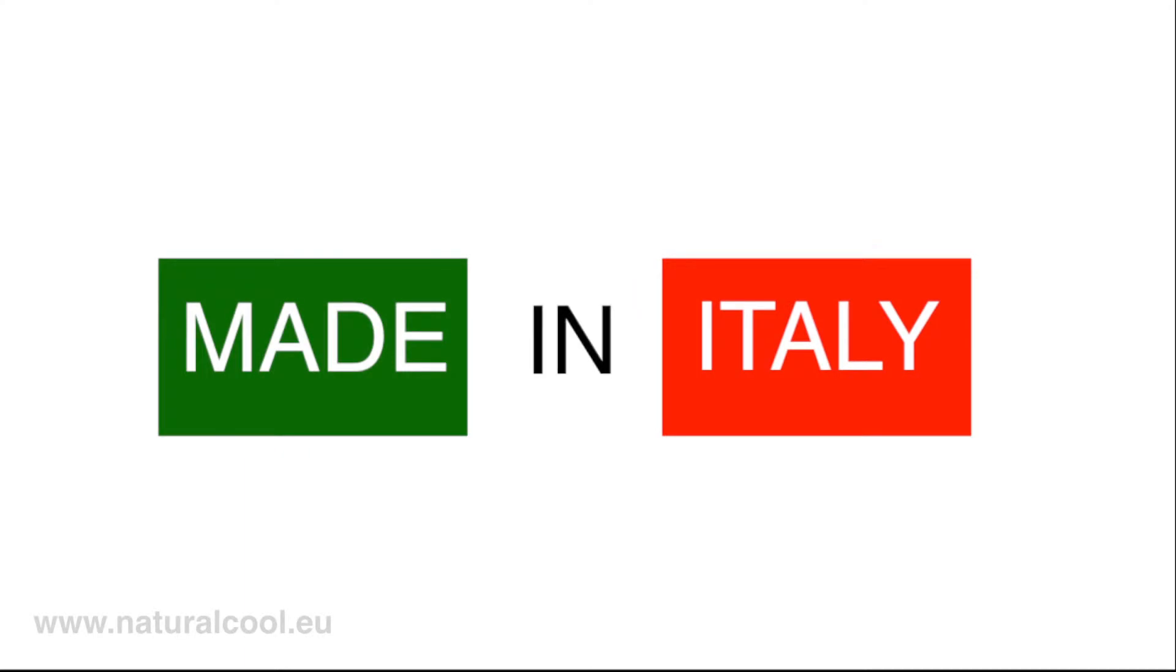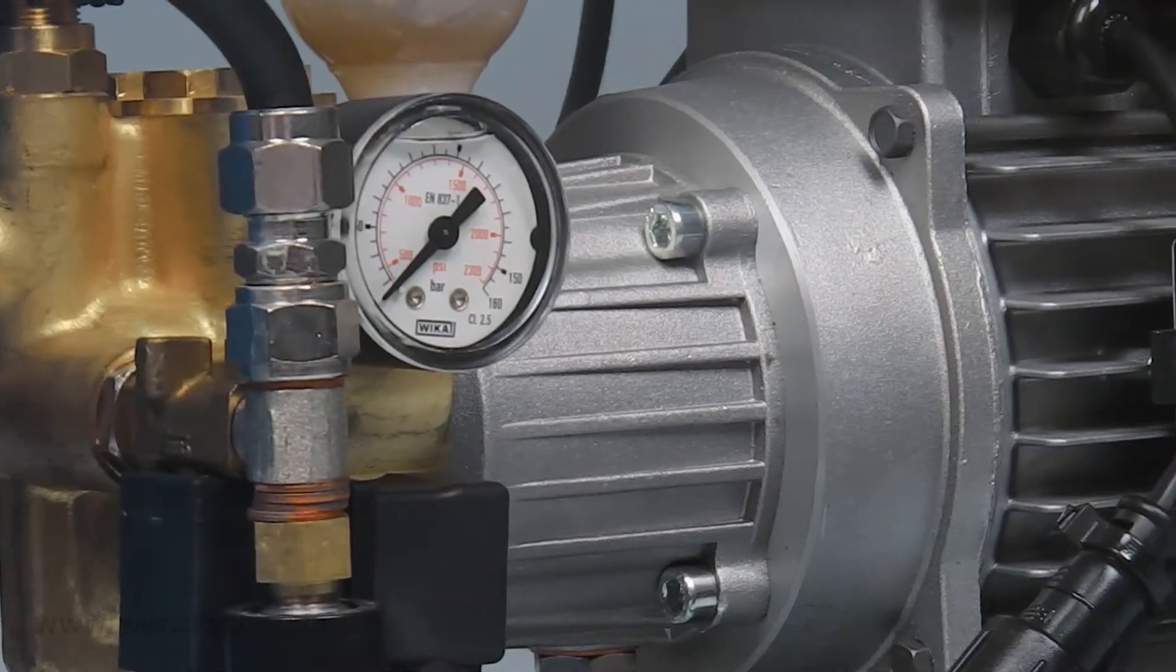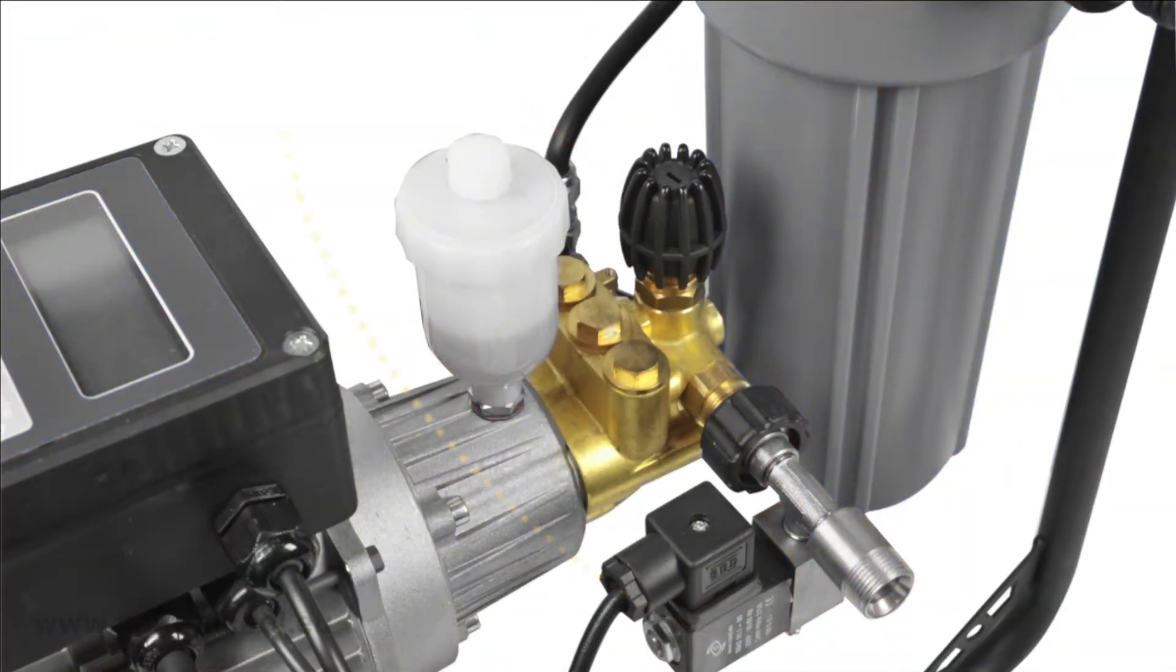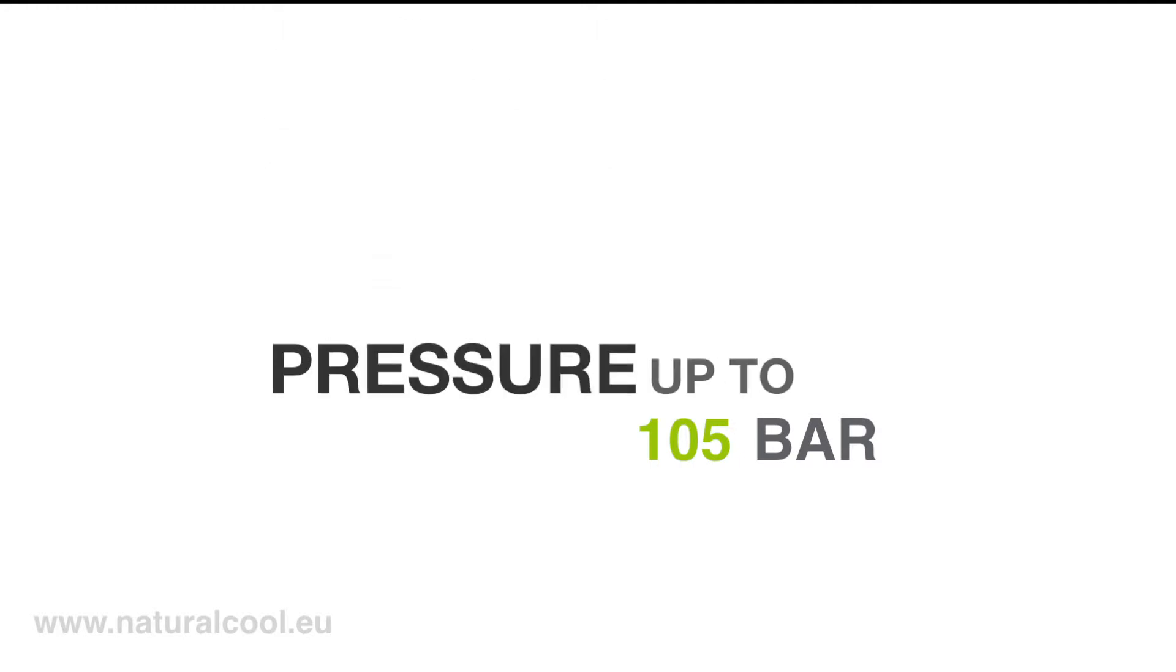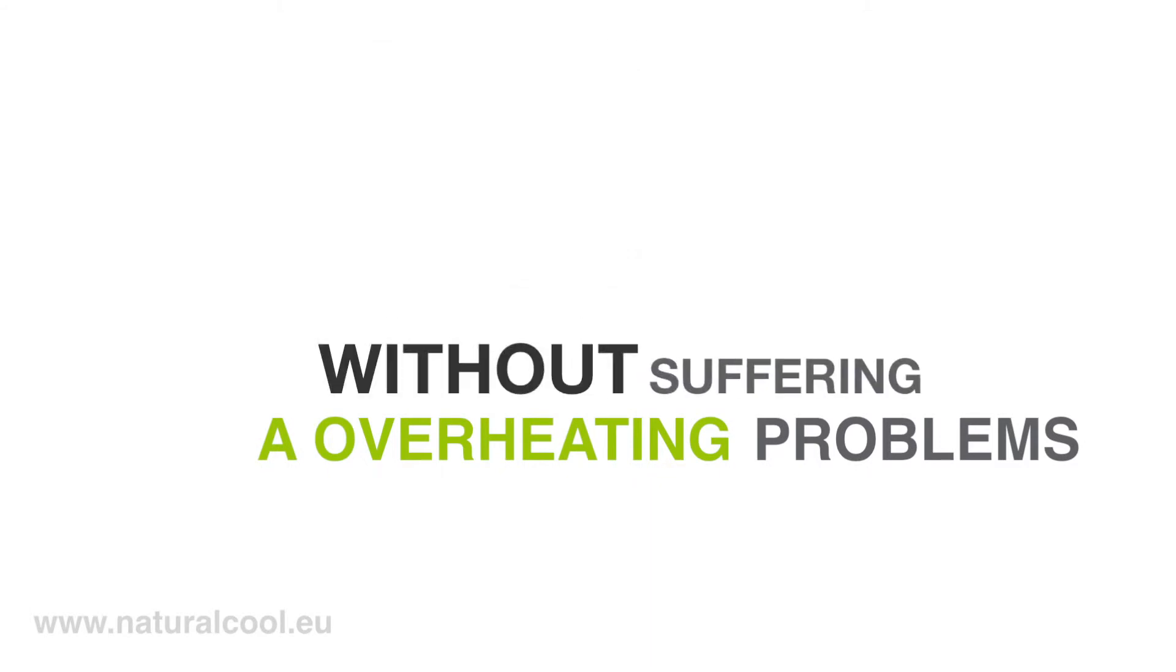EcoEvo has a distinctly Italian strong heart. A pump specially designed for the atomization of water that can work at a pressure of up to 105 bar. Thanks to a flow rate valve, this pump can work at a very low capacity without suffering overheating problems, a phenomenon known as bypass.